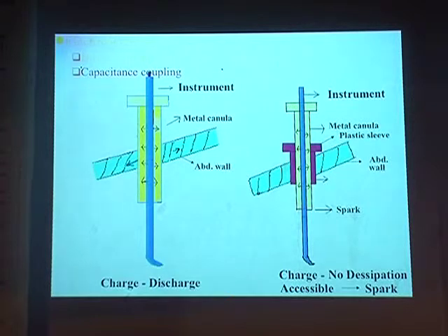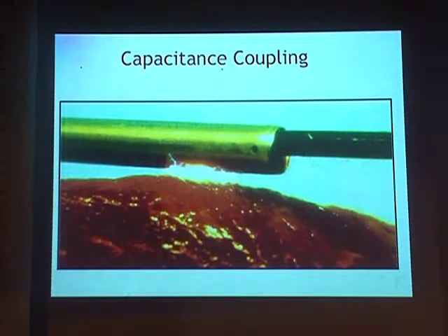So to protect against this, if we are using metallic trocars and a plastic sleeve, the best approach is to take out the metallic trocar from time to time and rub it against the patient, so it is grounded. The static electricity should be grounded in a cycle, so that it will not build up. Otherwise it can touch the tissue and cause a burn.